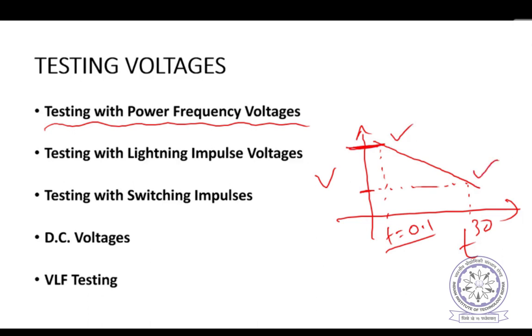Therefore, at a little higher stress also we will test. The test duration will be 1 minute as per standards. For 1 minute, the power frequency voltage is applied, and if it survives, the equipment is said to have passed the power frequency test. Apart from this, there is the lightning impulse voltage test and the switching impulse voltage test. We will see exactly what these are later.